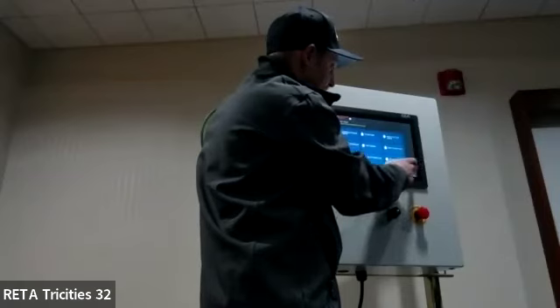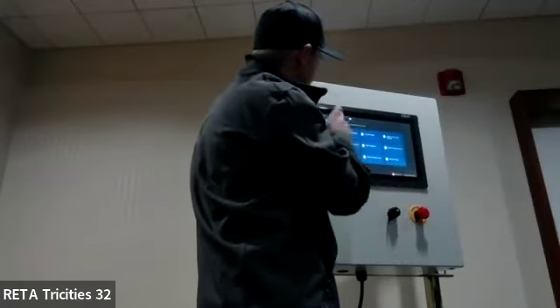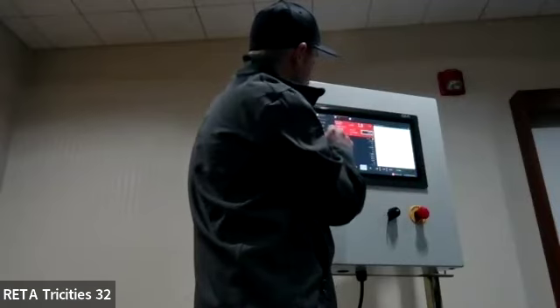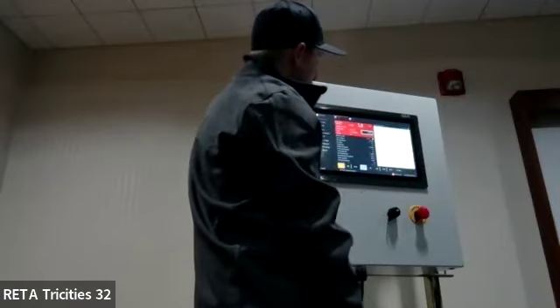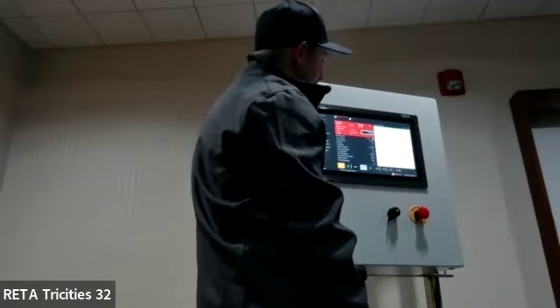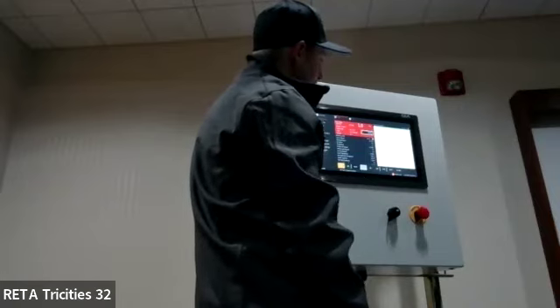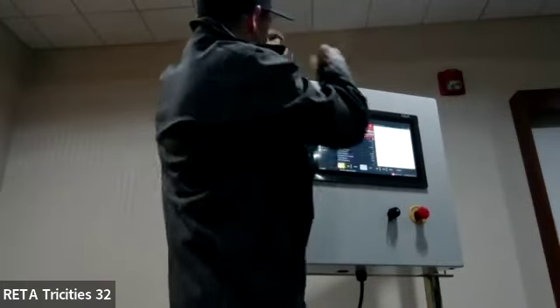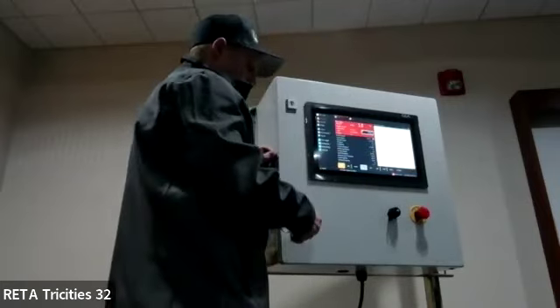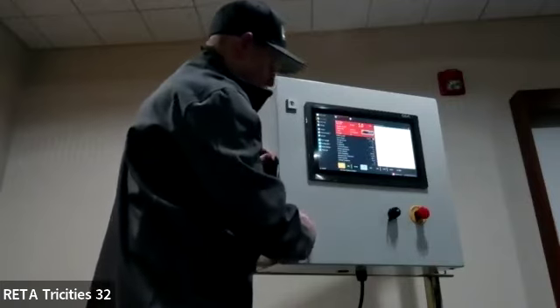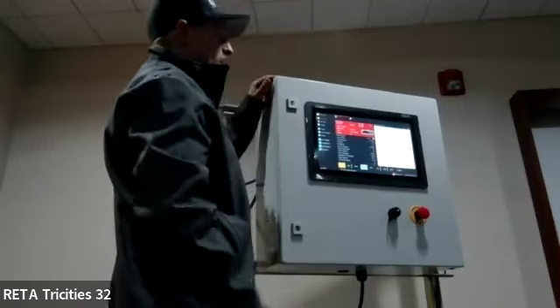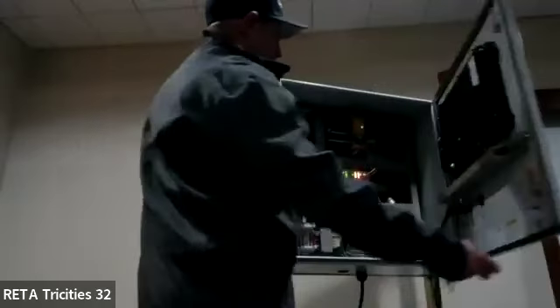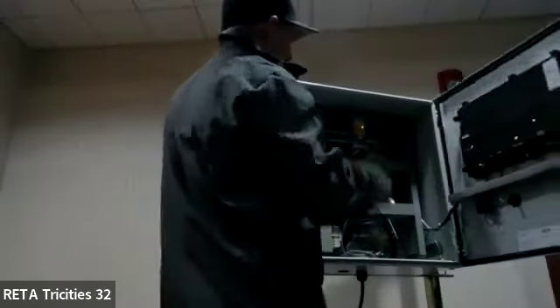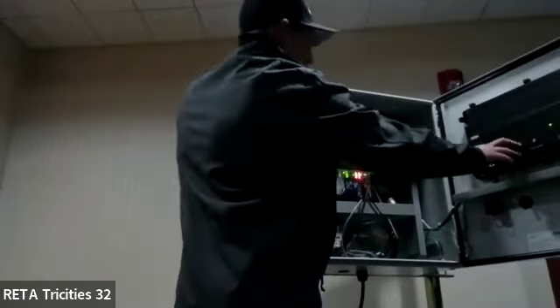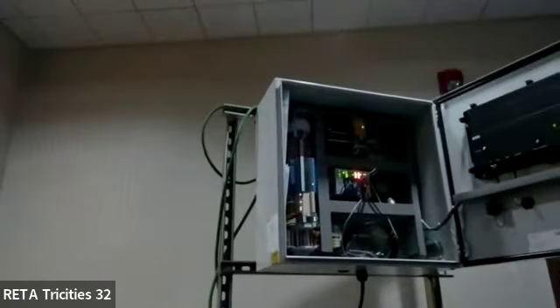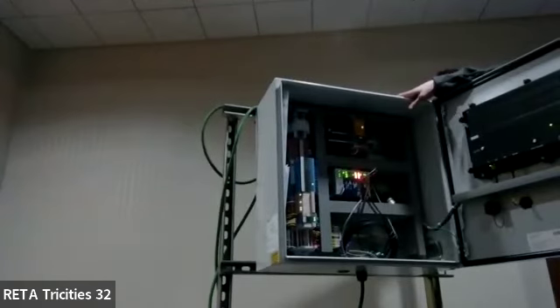This specific panel is designed to handle all situations, liquid injection, thermal siphon, whatever. It's got the additional relays in it so that we can configure the panel to anything we want. So this is one of our stock panels. You may not get that on a panel that we order specifically for a piece of equipment. But if somebody is in a situation where they need a replacement panel, this is the panel that we would bring out because it's configurable to everything.